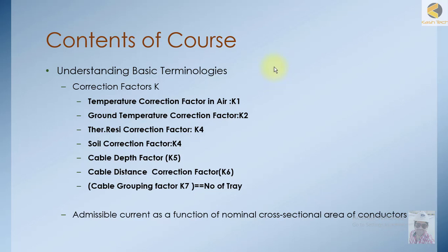In this section I will be explaining some more terminologies like correction factors. For example, if our cable is designed for 2 amperes and you are running this cable single in conduits or running it with 10 or 20 cables together, they will add to the heating effect. The heating from other cables will be added to this cable, so if there is a source of heating, the cable cannot be used with the same rating as supplied.